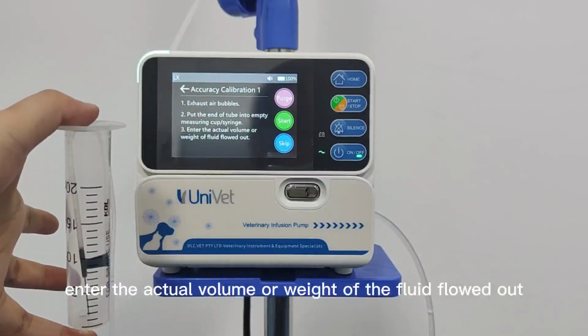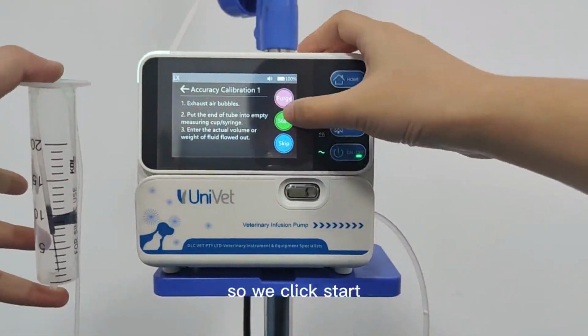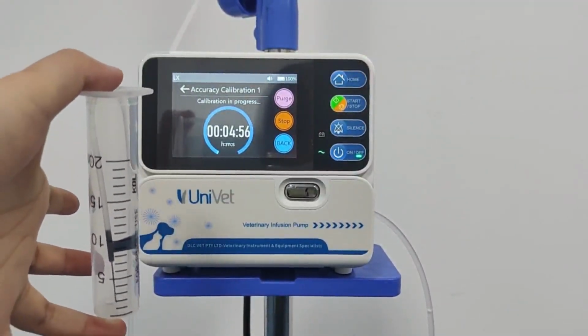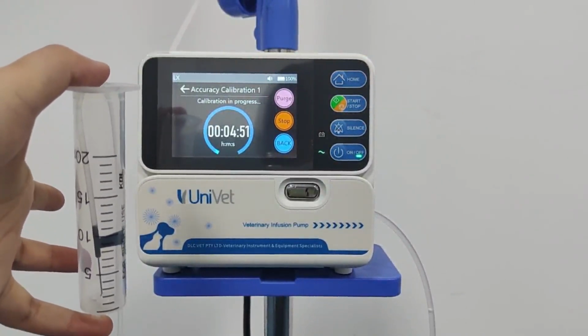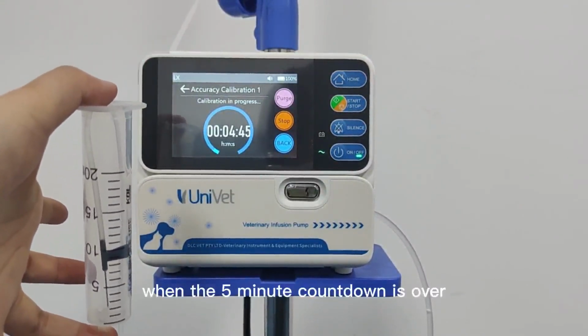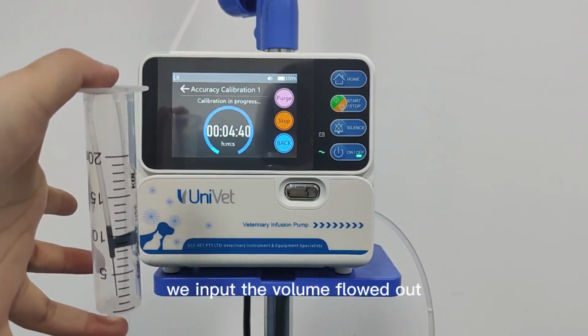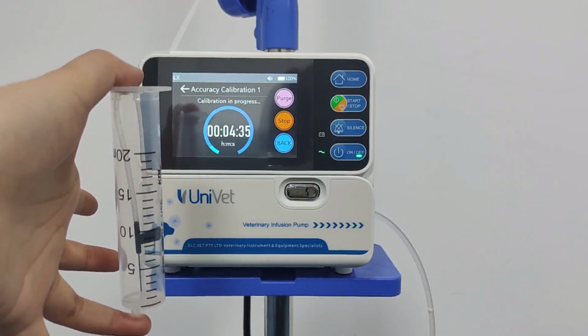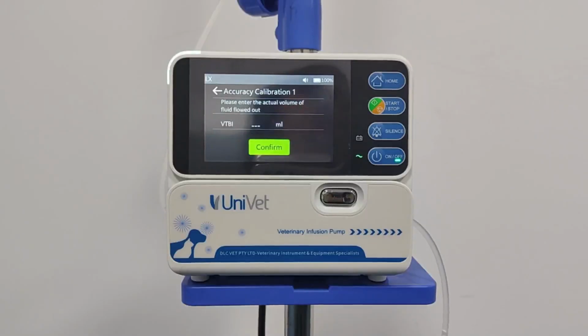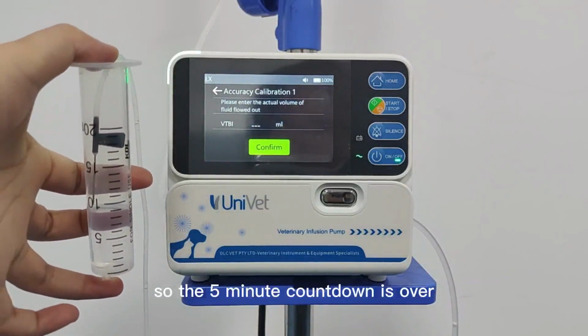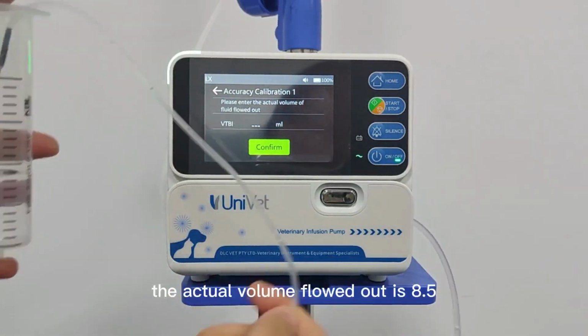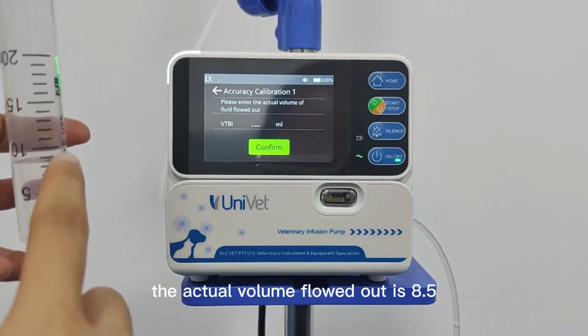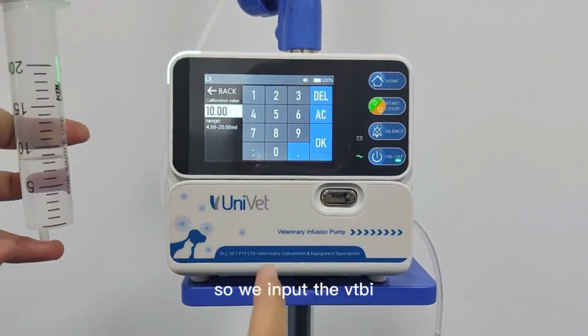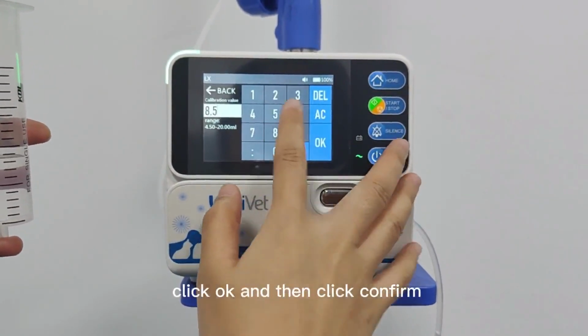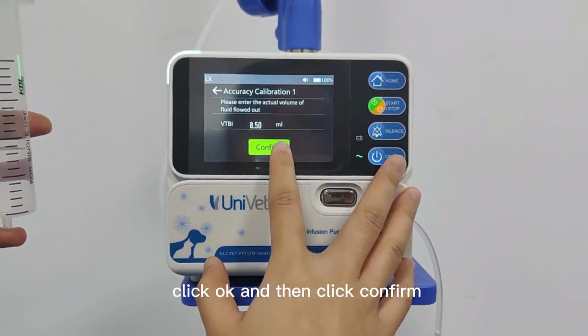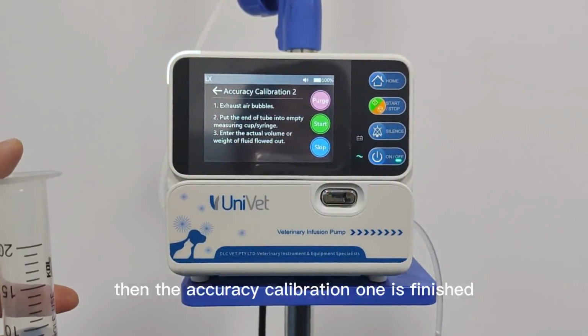Enter the actual volume or weight of fluid flow out. So we click Start. When the 5-minute countdown is over, we input the volume flow out. So the 5-minute countdown is over. The actual volume flow out is 8.5. So we input the VTBI, 8.5. Click OK. And then click Confirm. Then the accuracy calibration 1 is finished.